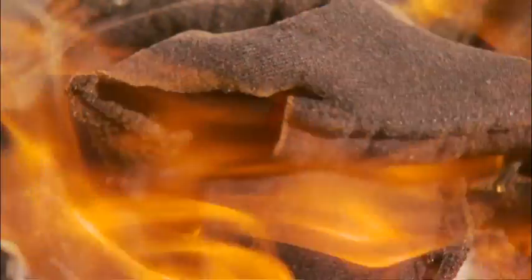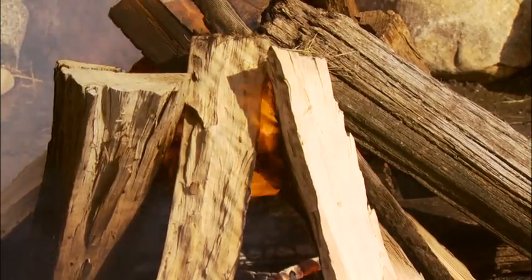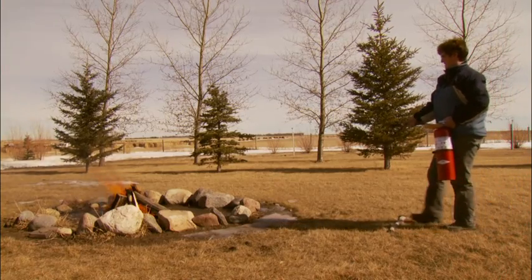So a fire starts. It's quite small and you feel you can put it out using your ABC fire extinguisher. How do you actually do it? First, pull the pin at the top of the extinguisher that keeps the handle from being accidentally pressed. Second, aim the nozzle towards the base of the fire, not directly into the flame. Aim away from yourself and from others, upwind if possible.